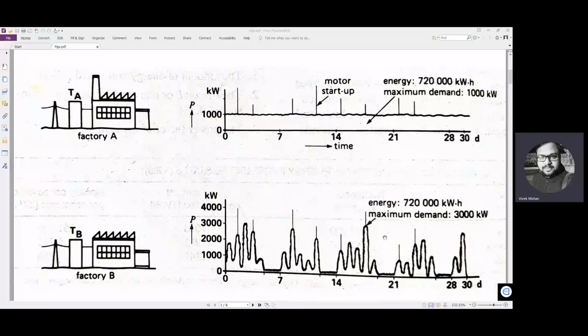I hope you can see this figure. See the monthly cost of electricity supplied to a large customer. It depends not only on the energy consumed, but also upon the rate at which it is used, or based on kilowatts also, as we have seen. Not only on kilowatt hours, it depends on kilowatts also. So the cost also depends upon the active power, kilowatts, drawn from the line.